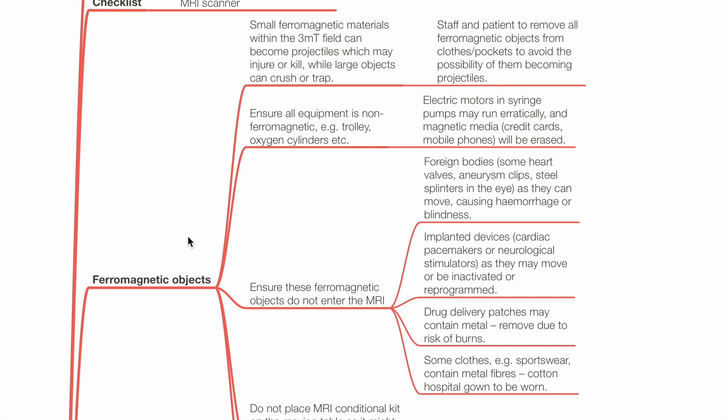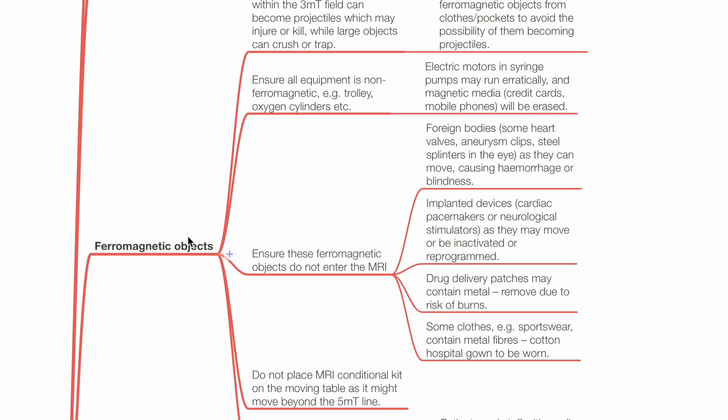Electric motors in syringe pumps may run erratically. Magnetic media such as credit cards and mobile phones will be erased. Ensure these ferromagnetic objects do not enter the MRI.